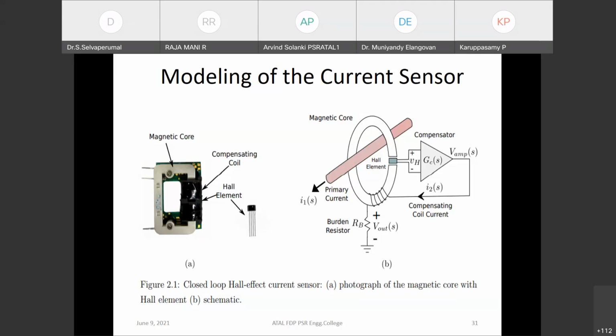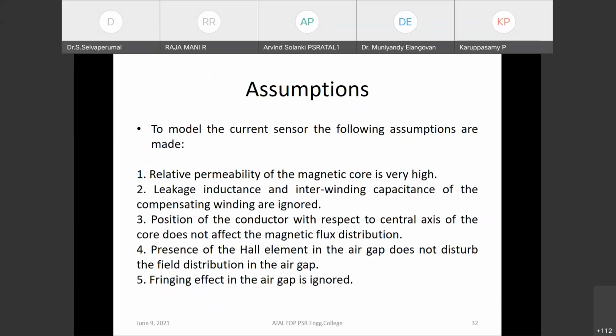Some assumptions are made to model the current sensor: the relative permeability of the magnetic core is very high; leakage inductance and interwinding capacitance of the compensating winding are ignored; the position of the conductor with respect to the central axis of the core doesn't affect the magnetic flux distribution; the presence of the Hall element in the air gap doesn't disturb the field distribution; and the fringing effect in the air gap is ignored.